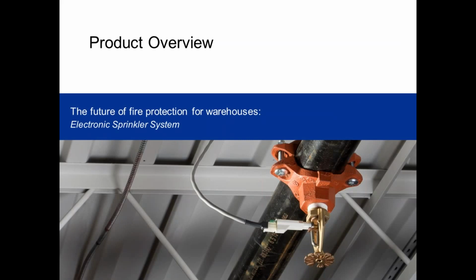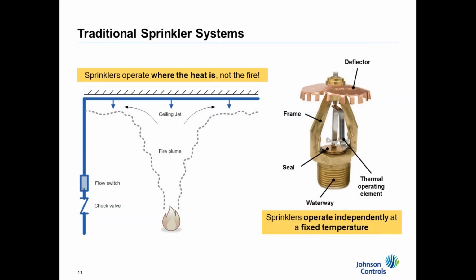So I wanted to go through an overview of where the technology is now heading with this first release of an electronic sprinkler. In order to understand that, we have to look at generally how traditional sprinkler systems work, especially the thermally operated ones. It's not necessarily where the sprinkler is located in relation to the fire. It is where the heat plume is that activates the sprinkler. So if you've got a facility that's 40 or 50 feet tall, or even 20 feet tall with an airflow through it, like a large fan, that is going to change which sprinkler head will be affected, because you're waiting for the heat to activate that thermal sensor element, whereas you're looking for the jets and the fire plume. So the fire could actually be 15 feet from where the first sprinkler activates.